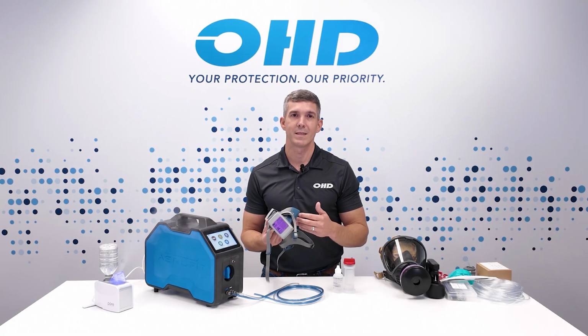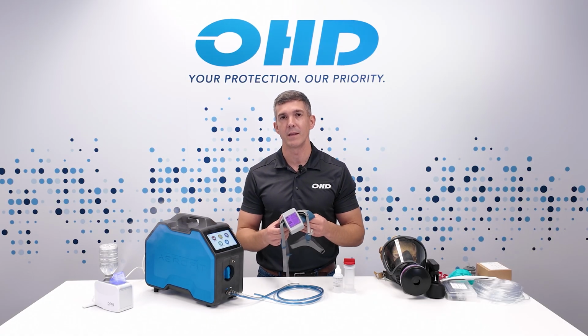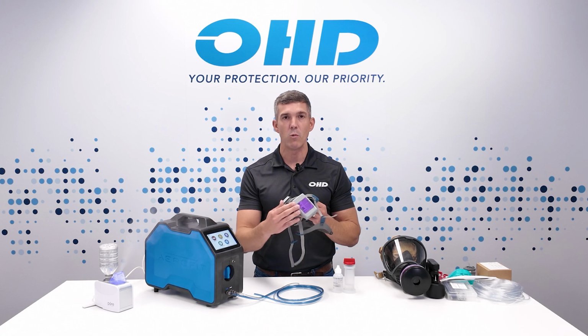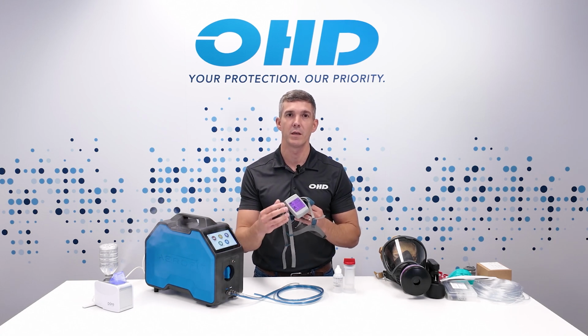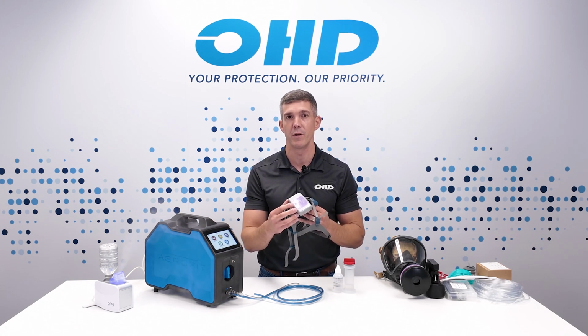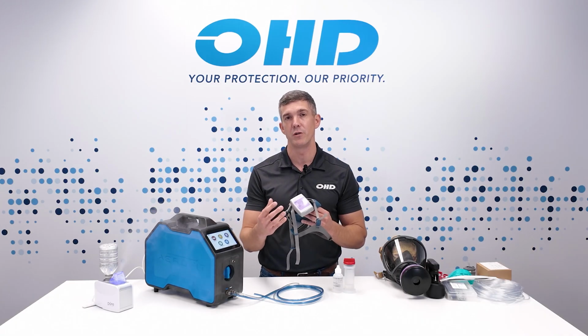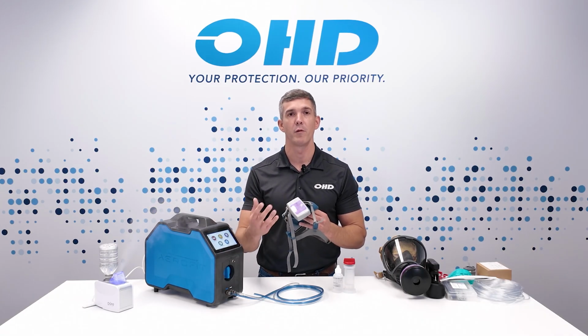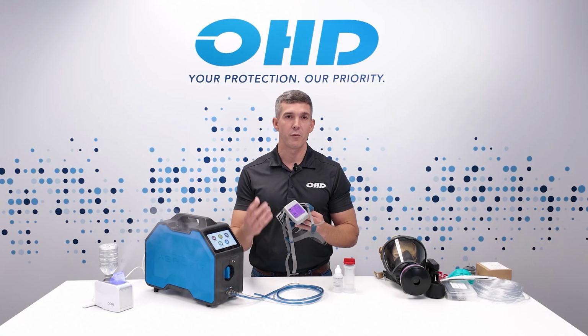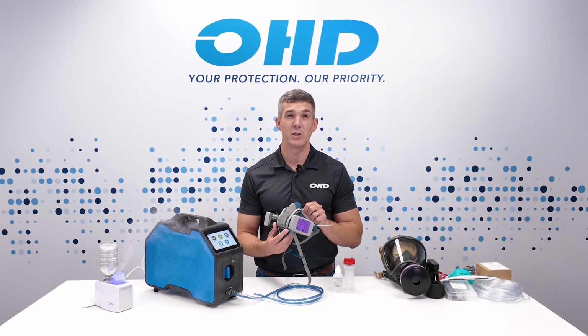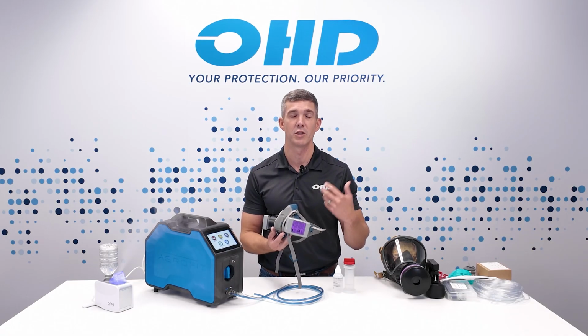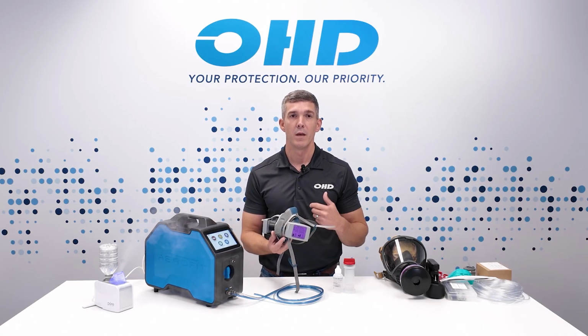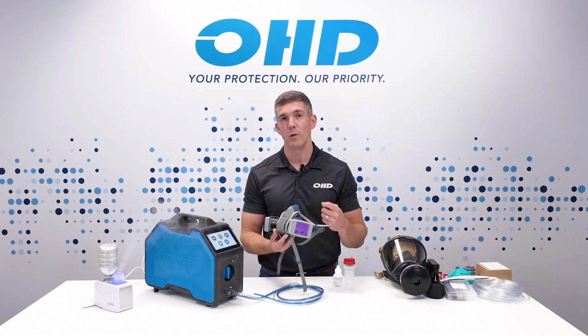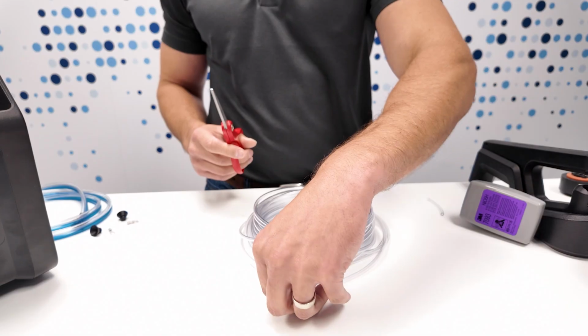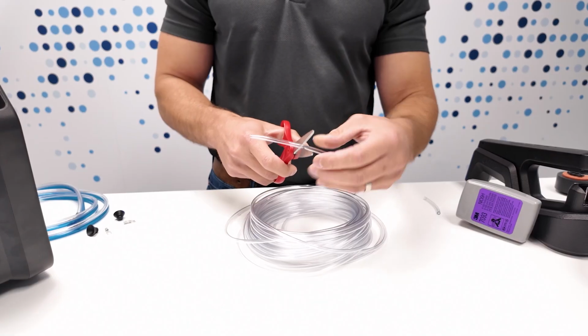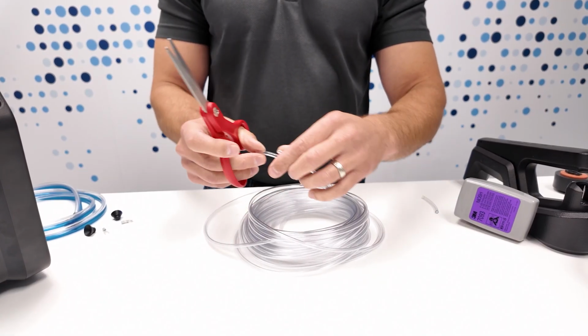For elastomeric testing with any CNC instrument like the AeroFit, it will require P100 filters, so particulate can be filtered out before entering the respirator, confirming that any particles measured inside of the respirator are from leaks. Adapters for the 3M respirator and other respirators can be sourced from a number of sources as well as directly from OHD. Before we attach the adapter, we'll need to cut a sample tube to run inside of the respirator for sampling in what's called the breathing zone.